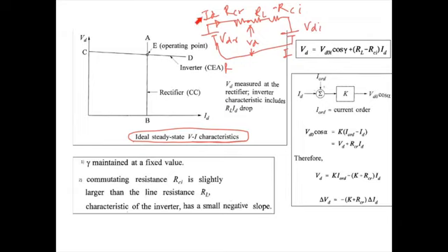This equilibrium gets disturbed if the input AC voltage on the rectifier side or on the inverter side changes. As we discussed previously, if the inverter voltage increases or decreases, then Id changes, and therefore some control action is necessary in order to restore the current in the DC link to a constant value.